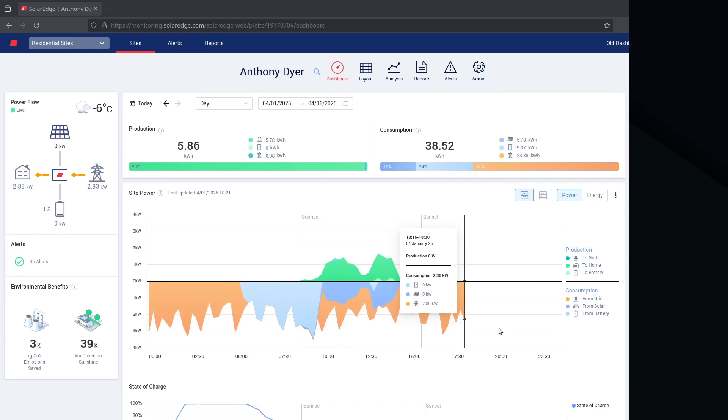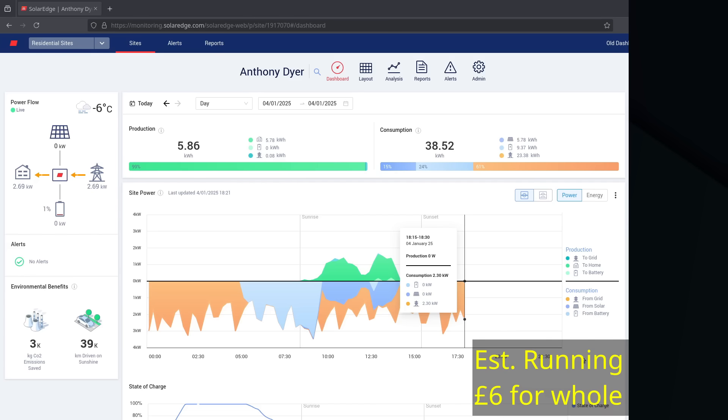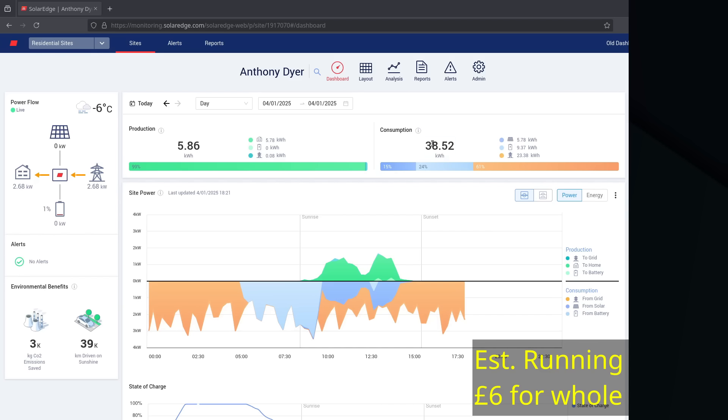So that is a typical anatomy in terms of power production and power consumption for my house. That's very impressive, 38.5 kilowatt hours. That is for not just running the heat pump but also running the house as well. Typically about seven or eight kilowatt hours will be used for household loads. I'm not charging up the car at all today.